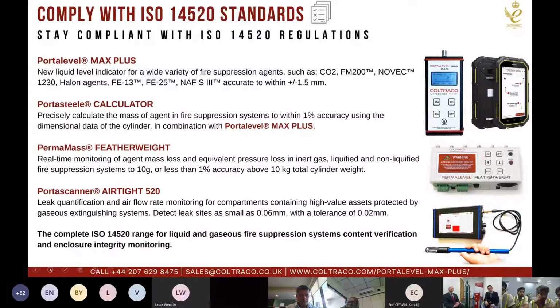At Coltraco Ultrasonics, we manufacture a range of other instruments to complement the ISO 14520 standards. The Portalevel Max Plus is what we are showing today, and I will also be showing you the Portasteele Calculator. The primary purpose is to calculate the weight of agent in all fire suppression systems to within 1% accuracy. As you probably know, the ISO 14520 standards mandate a contents loss limit of 5% or 10%, and the Portasteele calculator calculates that for you, so you know that your cylinder is within tolerance, and if it's not, you can replace the cylinder or refill it.